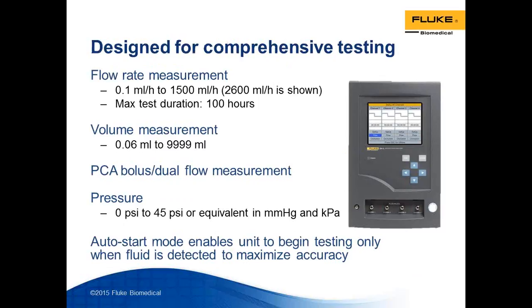Now, speaking of individual specifications, the IDA-5 is designed for comprehensive testing. It has a flow rate measurement starting from 0.1 milliliters per hour to 1,500 milliliters per hour. 2,600 milliliters per hour is shown, which means that Fluke Biomedical specifies the accuracy up to 1,500 milliliters per hour, but users can test up to 2,600. The maximum test duration is about 100 hours, so you can continue testing for 100 hours nonstop on any pump, and the analyzer will do fine. This is very common in some other countries around the world, by the way, the long duration of testing. The volume measurement is up to 10,000 milliliters.